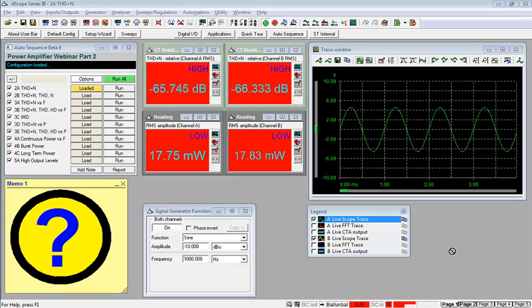For the benefit of those of you using a Mac who can't see these questions, the options are: this test could have failed perhaps due to excessive low order distortion; perhaps excessive high order distortion; maybe some excessive broadband noise, the N component; maybe too much mains hum in the result; maybe some other reason that we haven't listed; or perhaps you just simply don't know.